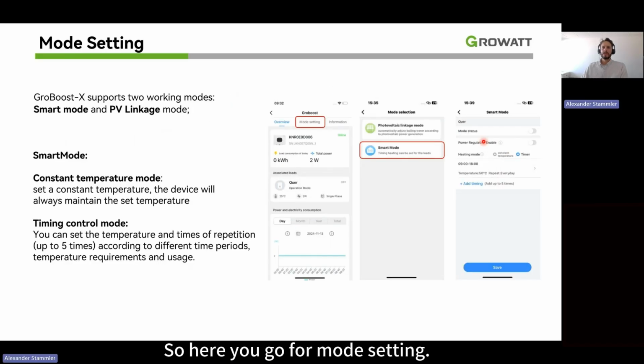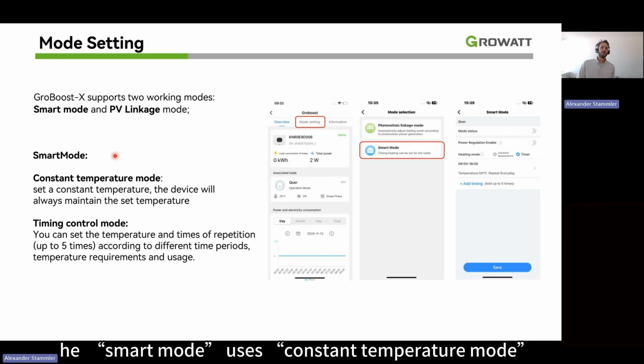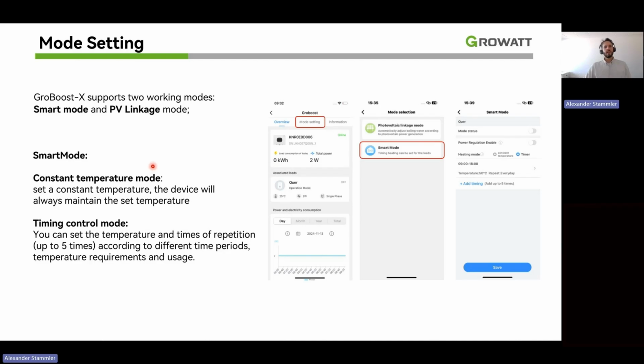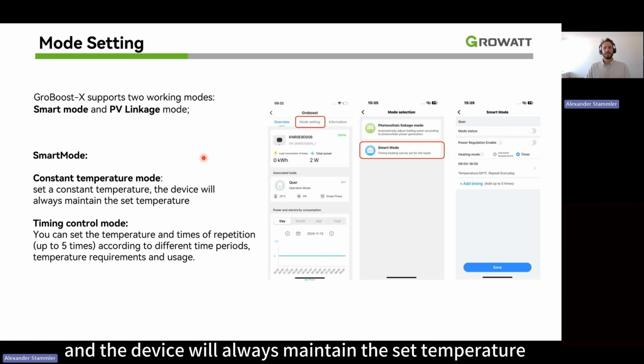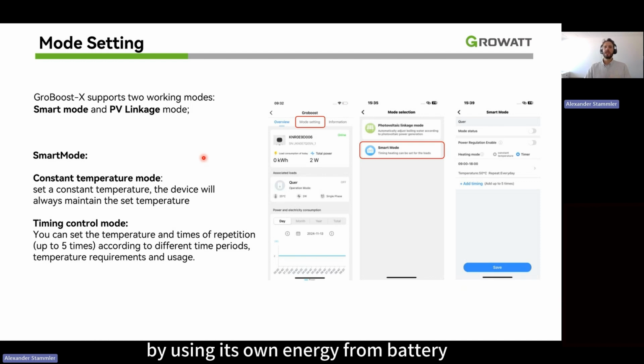Yeah. So here you go for mode setting, and you have the two different modes. One is smart mode, the other is photovoltaic linkage mode. The smart mode uses constant temperature mode. It sets a constant temperature, and the device will always maintain the set temperature by using its own energy from battery, from PV, or from grid.